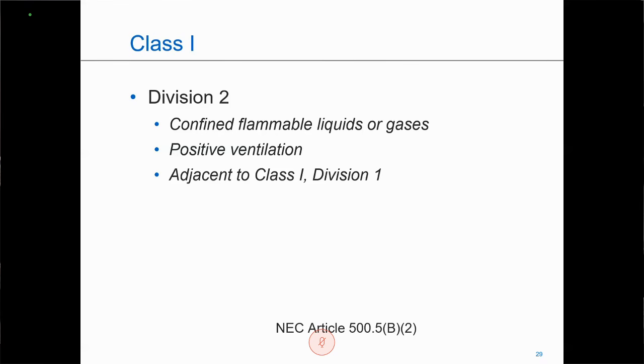Now, not every envelope is always 3 feet. It just depends on the particular application. So, for example, a gas station, we stop at them multiple times a week to put gas in our car. When we pull up to the gas station, 18 inches on each side of the pump is a Class 1, Division 2 area. 18 inches up from the ground in a 20-foot diameter out from that pump in all directions is a Class 1, Division 2 area. And a sump underneath the pumps would be Class 1, Division 1. So here's a perfect example where in that application, the envelope of the Division 2 area is different than it is with the paint booth example.